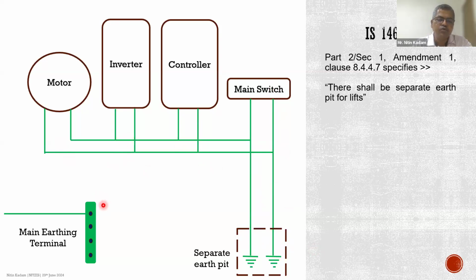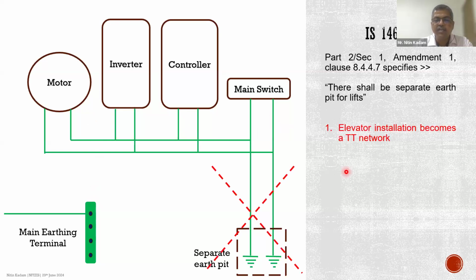Unfortunately, in most of the installations, there is no connection going from the main earthing terminal to the equipment for the elevator installation. So there is no connection from this MET terminal to the motor, the inverter, the controller or the main switch. So in a way, we are converting the elevator installation to a sort of TT network. Since there is a know-how gap in terms of the network types that are being supplied and the type of devices to be used on these network types, nobody is using an RCD in the circuit.